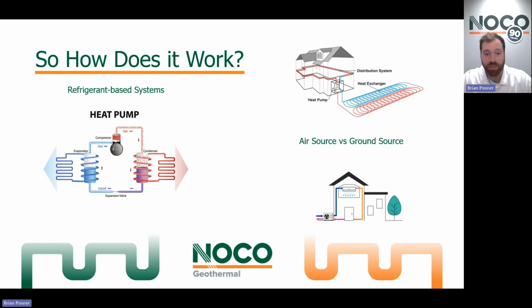With geothermal, it's the same process, the same equipment. However, we bury piping in the earth and use the piping in the earth as a heat sink rather than that outdoor fan unit. The benefit of this is that the earth is at a near constant temperature of 50 to 55 degrees. Meanwhile, the outdoor air temperature is usually the opposite of what you want it to be for its function. So to talk about heating, if you're trying to heat with air source heat pumps or anything using an above ground air exchanger, well, you're trying to pull heat out of 0 to say 10-degree winter air to heat a building. It's a miracle of science that we can accomplish this. It's very doable, but it requires quite a bit of electricity. And if that outdoor air exchange unit is covered in snow or ice, or it just physically gets plainly too cold outside for it to operate, it will shut off and you'll no longer have heating.